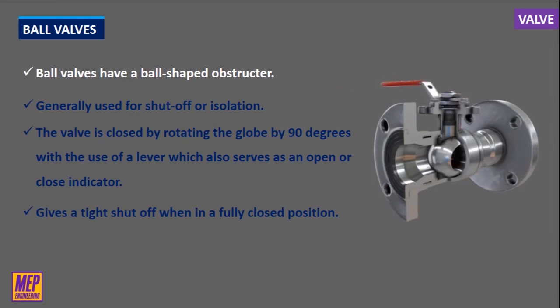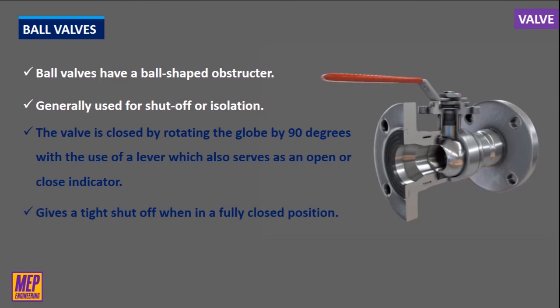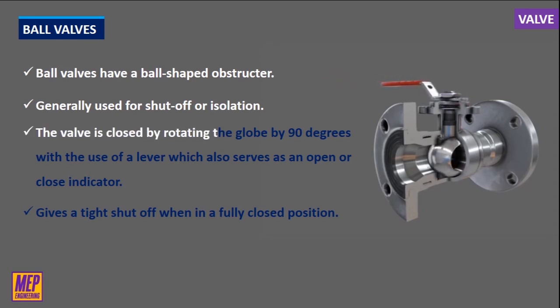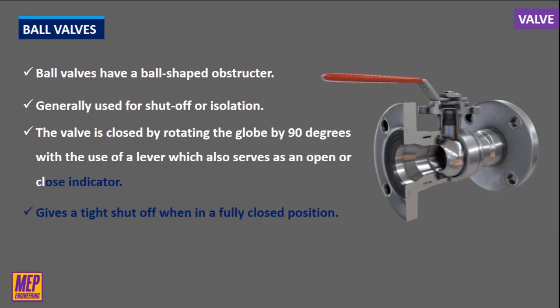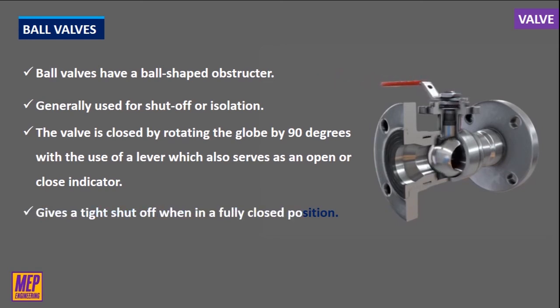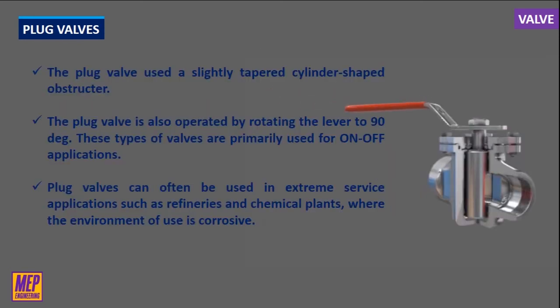Ball valves have a ball-shaped obstructor which is sandwiched between two cup-shaped seals. This type of valve is generally used for shutoff or isolation of the system. These valves are designed to be operated fully open or fully closed. The valve is closed by rotating the ball 90 degrees with the use of a lever, which also serves as an open or close indicator. The spherical plug gives precise control of flow and a tight shutoff when in the fully closed position.